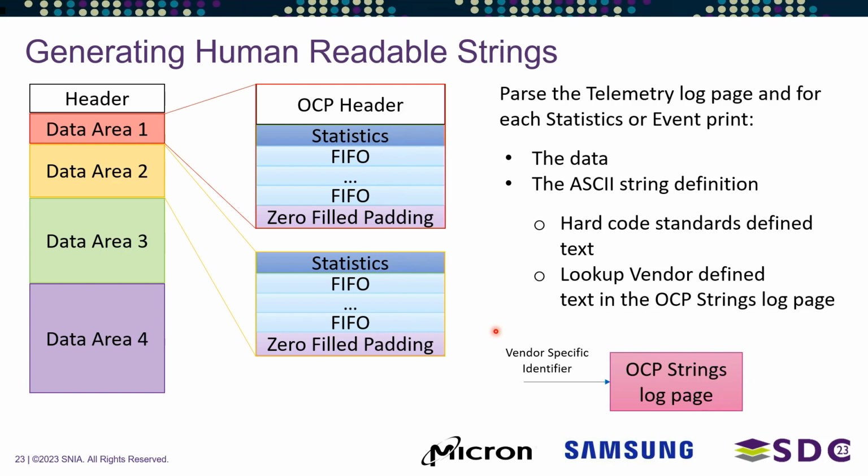Okay? So very early on, I was like, can I get 15-minute periodic sampling of 32 megabytes of data? And they went, absolutely not. That's way too much data. I'm not going to snapshot 32 megabytes of data areas 1, 2, 3 every 15 minutes for an entire fleet of drives and send it all through. And this is where we did come up with the idea that data area 1 is restricted in size. I think it's formally called out as 16 kilobytes. Something like that. Yeah, I think that's the number. So data area 1 is meant for periodic snapshots, maybe many times a day, of data then shared with the vendor, and it is limited to 16 kilobytes.